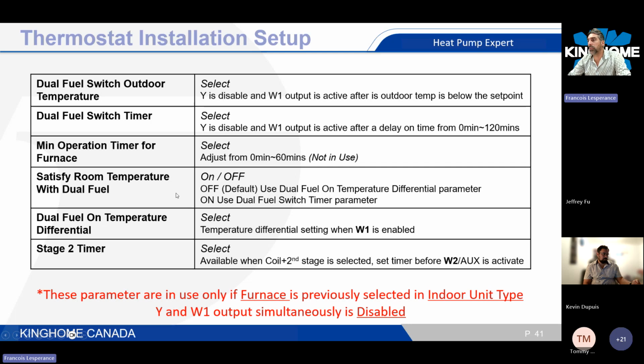Satisfy room temperature with dual fuel, where it's this one again. You're going to have to choose if you want to use the temperature differential or the switch timer. So basically you have here the next one, dual fuel on temperature differential. For example, you can put it on a 2 degrees Celsius differential, or you can use a timer saying after like 30 minutes of runtime of the heat pump, I want to cancel the heat pump and power on my gas furnace. And we have a stage 2 timer, only available when you have a 2-stage furnace selected previously. So now you have a timer between your W and W2. So there's a time delay over here.